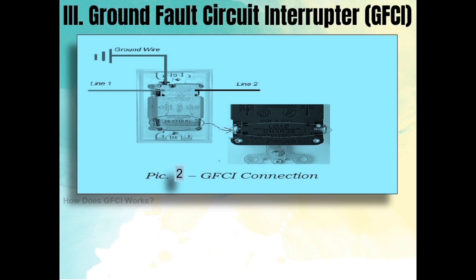How does the GFCI work? Normally, a determined amount of electric current passes from line 1 to load then back to line 2. When the GFCI senses a difference between the amount of electricity flowing into the circuit and that flowing out, even in the smallest amount, as small as 4 or 5 milliamps, the GFCI will react quickly to trip and shut off the circuit, preventing a possible electric shock.